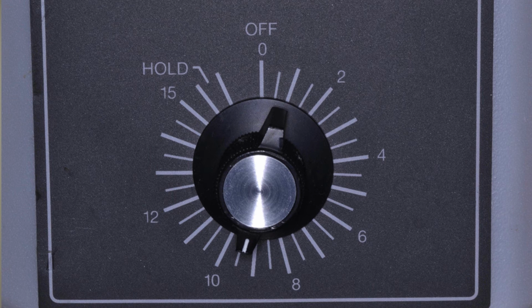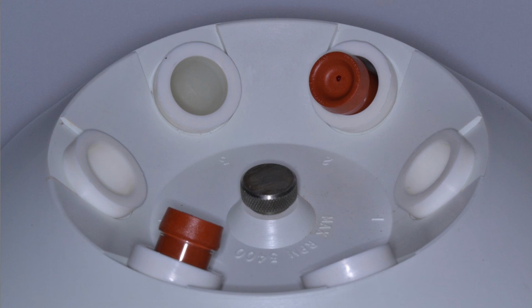You want to place the bottles across from one another so that they're balanced out. In this particular centrifuge, you can place up to 6 bottles. But as I'd already mentioned, as soon as you collect 4, start spinning them down. It's also important to balance the volume, so you're harvesting a similar volume in each bottle, because if the volume is off, that too will throw the centrifuge off.